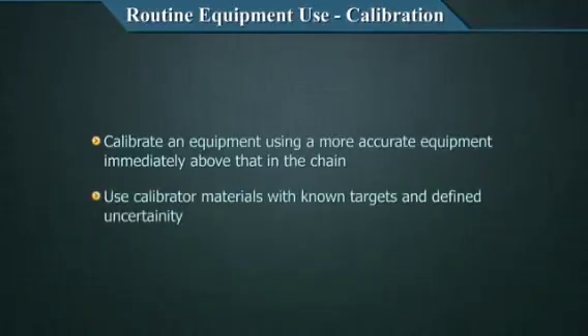And so now we have to understand how you calculate, compute and understand the amount of uncertainty of a calibrator or a calibrating system. And here I want to stop and tell you something that I had said earlier also: there are analyte calibrations as well as equipment calibrations. Let's consider equipment calibration as a kind of coarse tuning of your equipment and analyte calibration as a further fine tuning of your equipment.